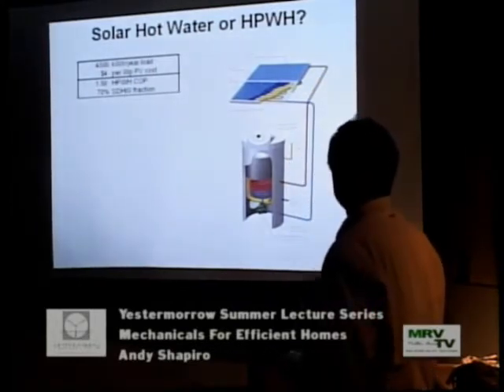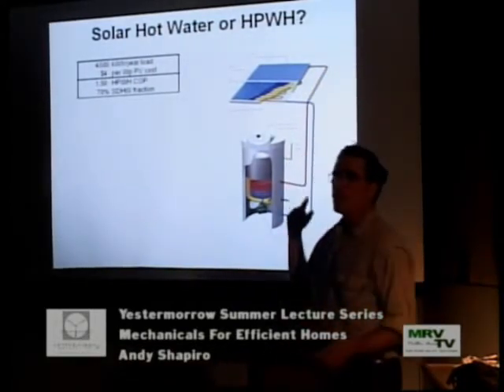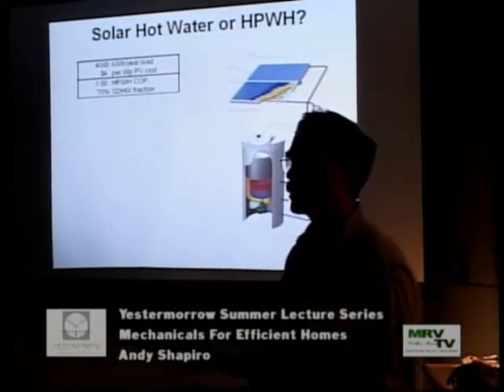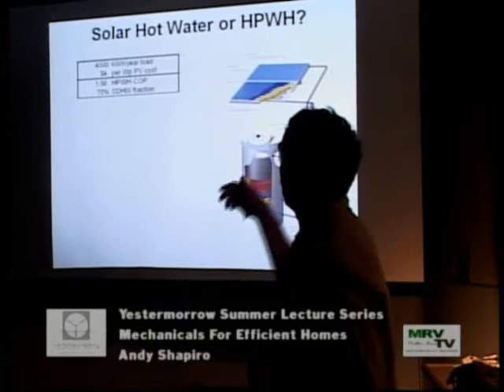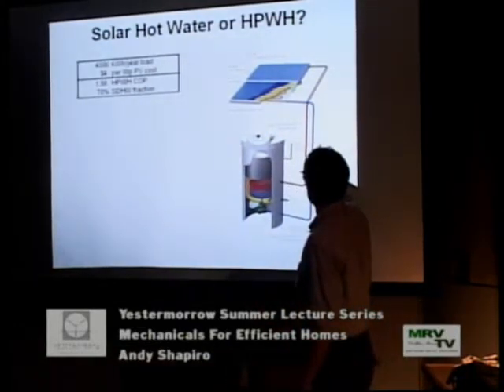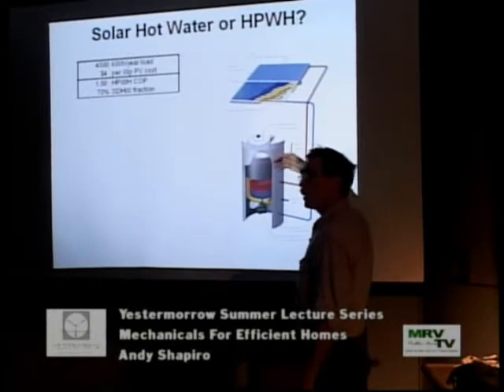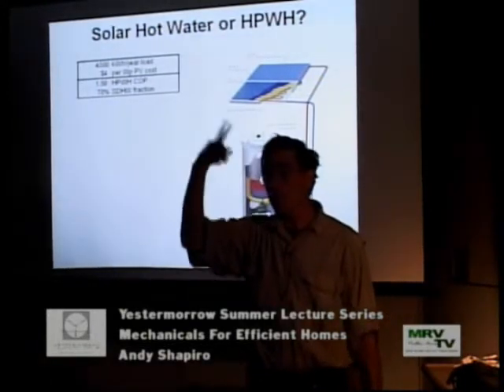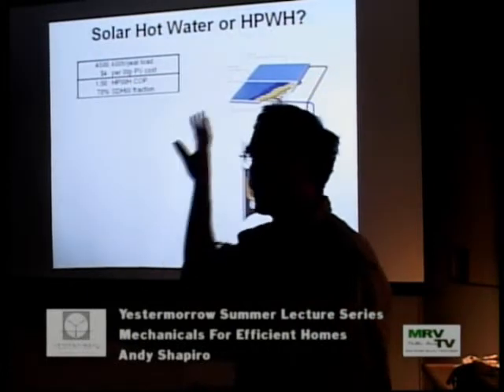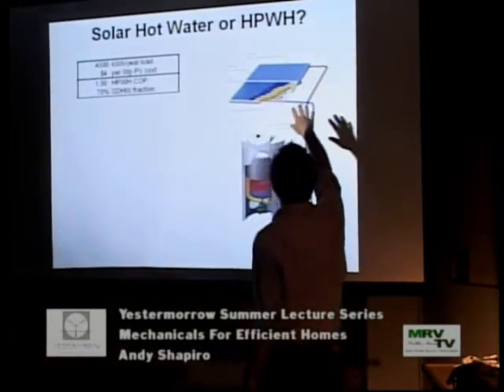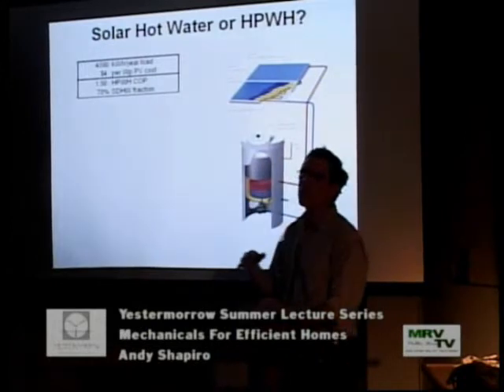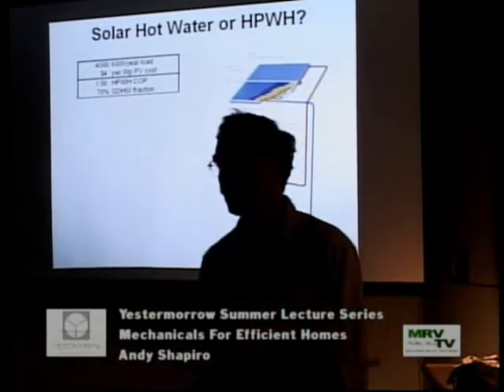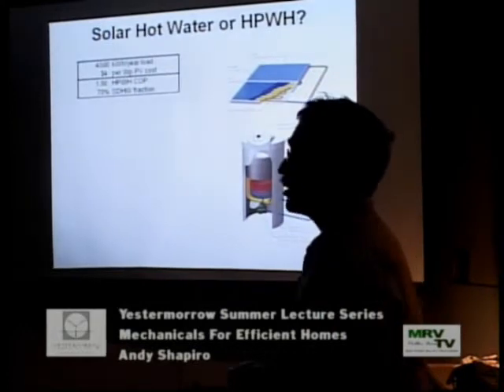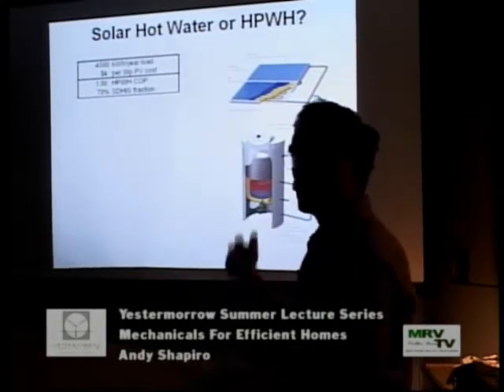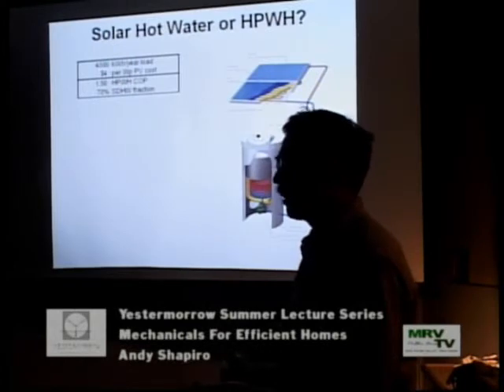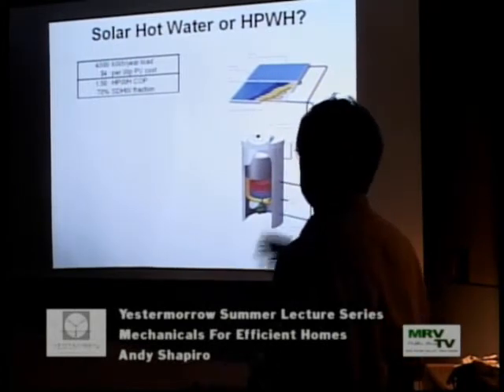That's a drain back. And the great thing about the drain back is when you go away in the summer and your tank would normally overheat and your collectors would overheat, it doesn't matter because there's no antifreeze in it. That's all down here once the tank is charged. One of the problems with regular solar hot water heaters with glycol in there, if you go away for 2 weeks, that glycol stagnates in here and you get 300 degrees or more in the collectors and it starts to break down the glycol. And eventually it gets acidic and it starts attacking the system. And it means you've got a maintenance visit. So it doesn't break down if you just keep track of the pH and you change it, but who does that? So anyway, I'm very high on this system.